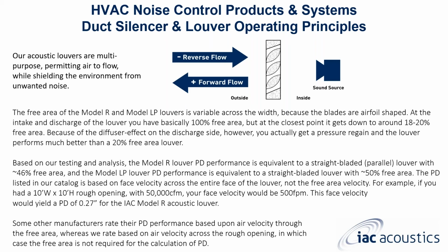But when you're designing louvers, design louvers to performance first. Percent of free open area is what it is. I've gone through this many times, and for a 10 foot opening, if you want a 50% free open area, it might actually have to increase to, say, 14 by 16 feet. The hole might already be open there, only at 10 foot by 10 foot, and you cannot increase it. That then becomes a problem. So again, if you want to go over this later at any given time, contact me. I would gladly go over this with you in more detail.